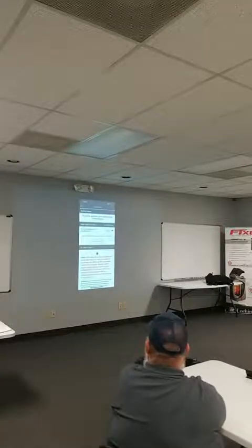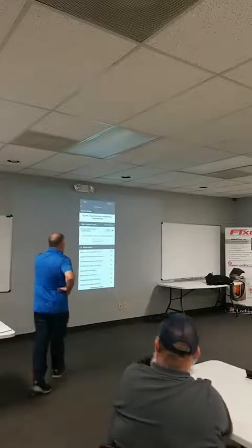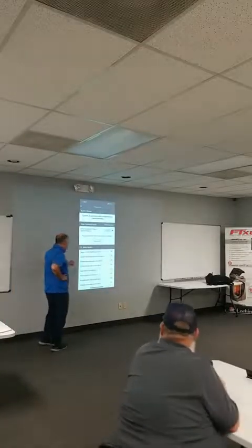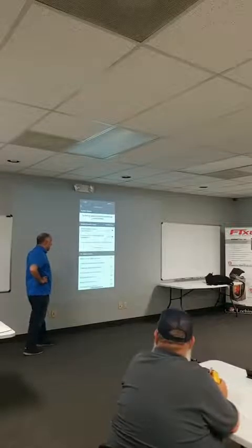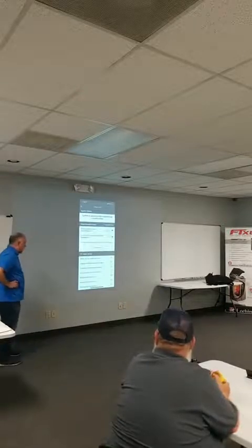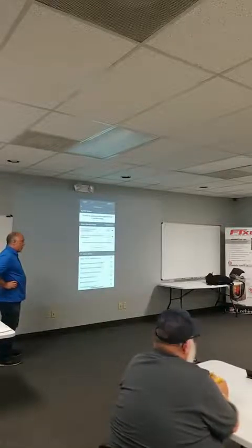If we tap on the minor faults, the liquid line temperature is too high, condenser pressure is too high, compression ratio is too high, approach is too high. Those are all symptoms of a dirty condenser. So go ahead and pull that back off there so we don't kill it.